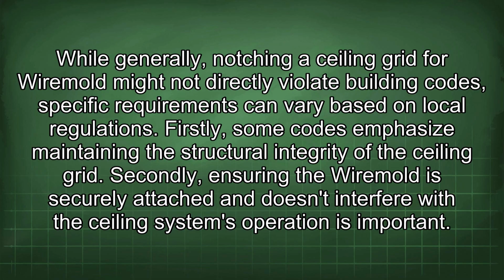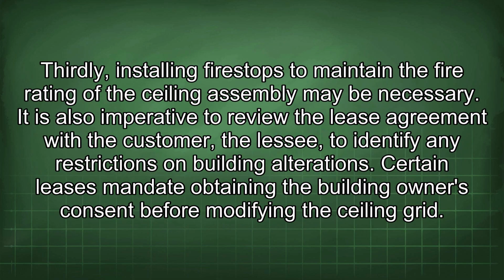local regulations. Firstly, some codes emphasize maintaining the structural integrity of the ceiling grid. Secondly, ensuring the Wiremold is securely attached and doesn't interfere with the ceiling system's operation is important. Thirdly, installing fire stops to maintain the fire rating of the ceiling assembly may be necessary. It is also imperative to review the lease agreement with the customer, the lessee, to identify any restrictions on building alterations. Certain leases mandate obtaining the building owner's consent before modifying the ceiling grid.